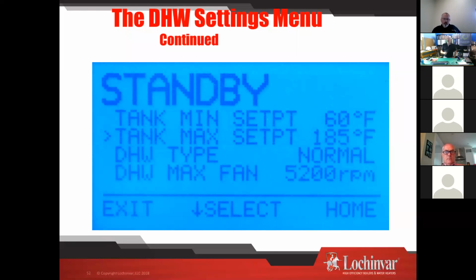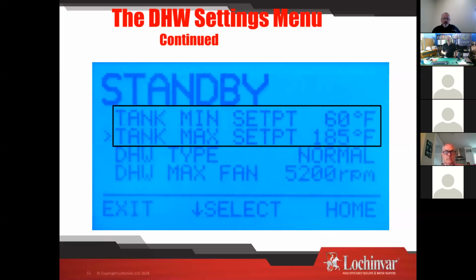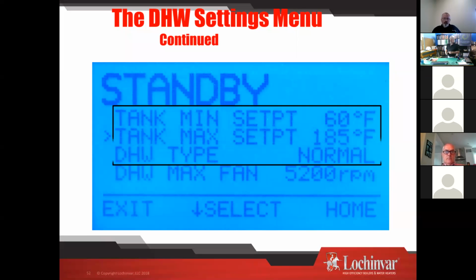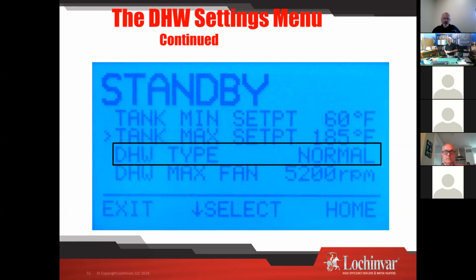Minimum maximum set point. Again, keep your homeowners safe from themselves right here. Usually that max set point should probably be somewhere around 140, 130, depending on whether you have a mixing valve or not. Again, keep them from setting it and scalding themselves. And then your minimum set point there, if you want to keep them away from a no hot water call, where they adjust that and get into it. Let's talk about types of domestic hot water. Boiler will operate what we call normal or zone. Now, normal is I'm piped right off of my boiler.